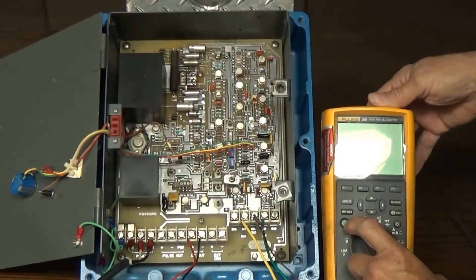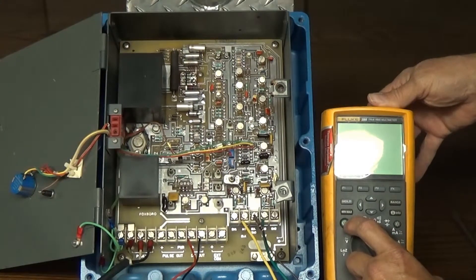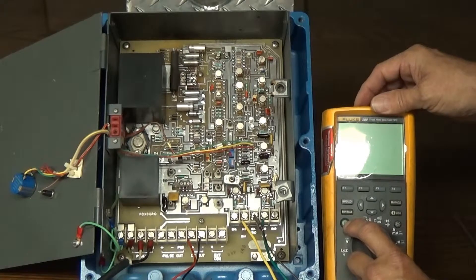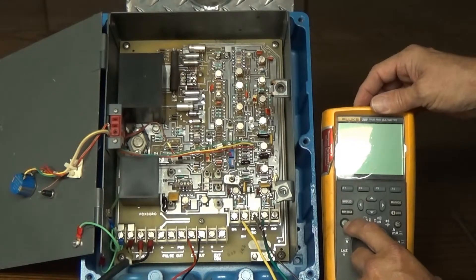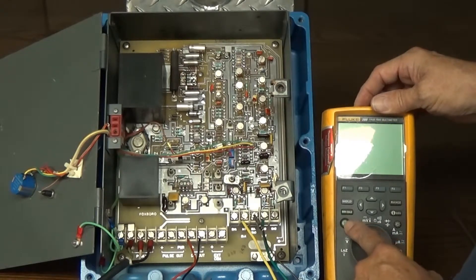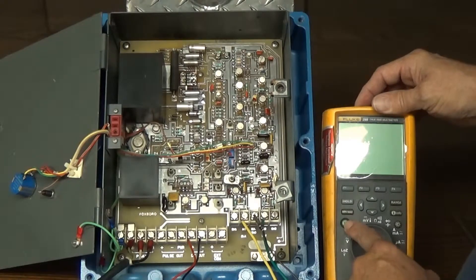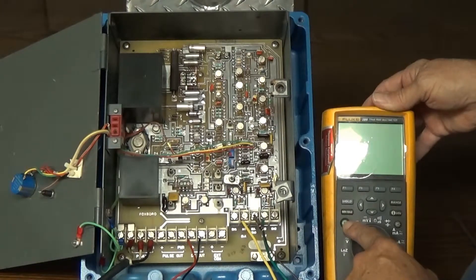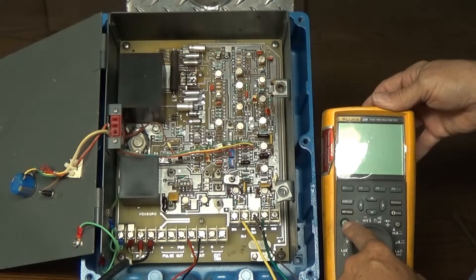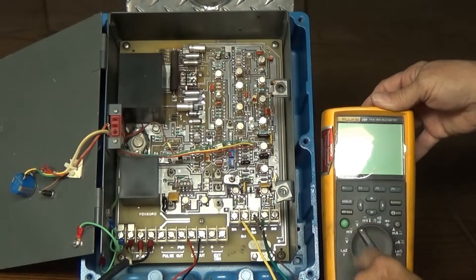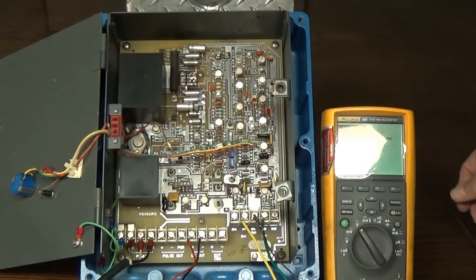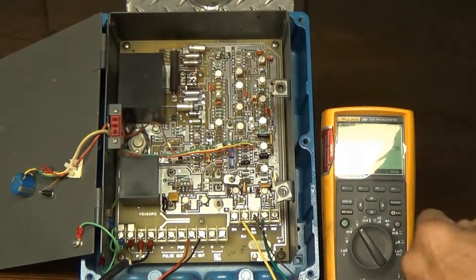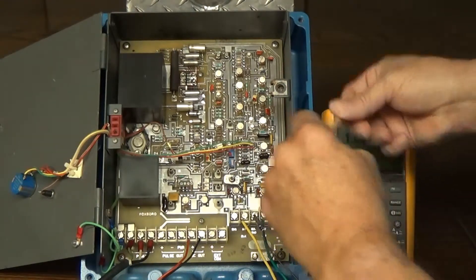You can calibrate your zero by tuning for either 4 milliamps or 1 volt, depending on how you're wired up. I'm reading across a 250 ohm resistor, which means we're calibrating for 1 to 5 volt range and zero has to be at 1 volt. And I'm reading that with this multimeter here, which we'll power up in just a second here at 1.0028 volts.